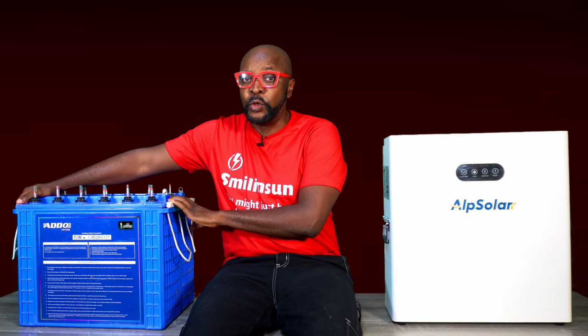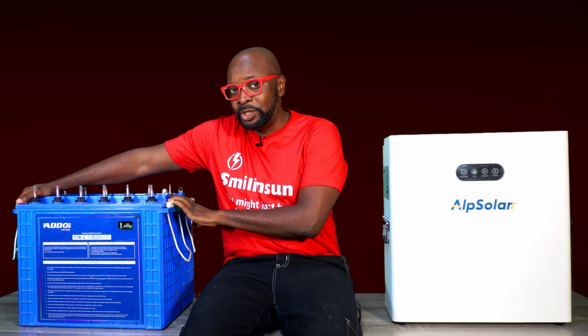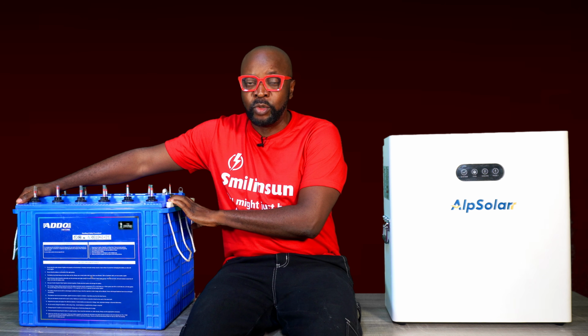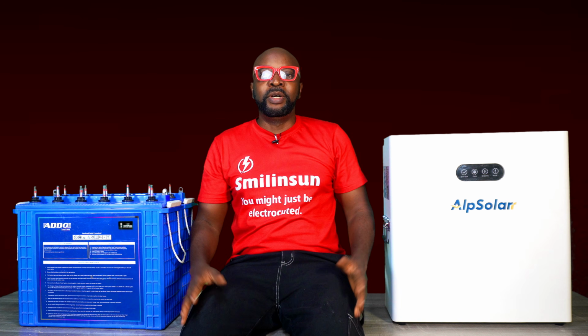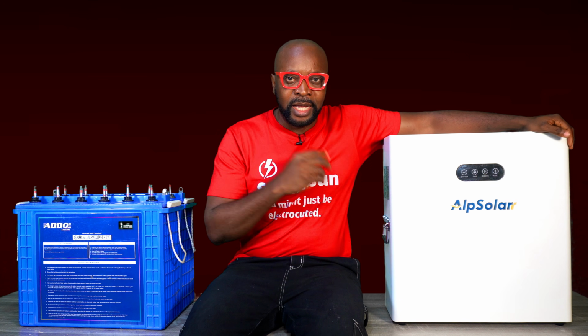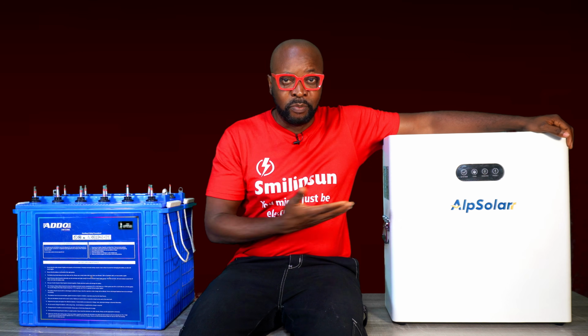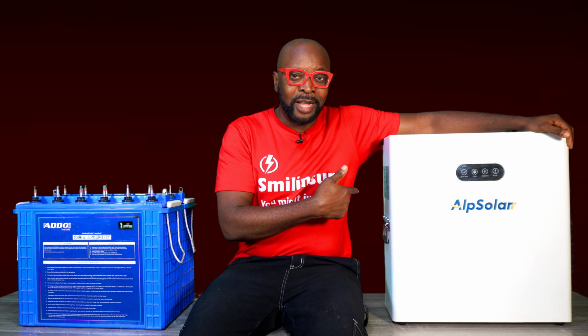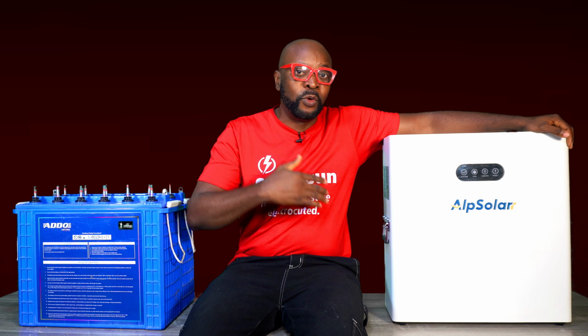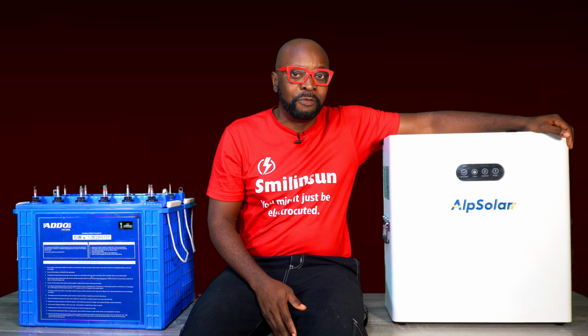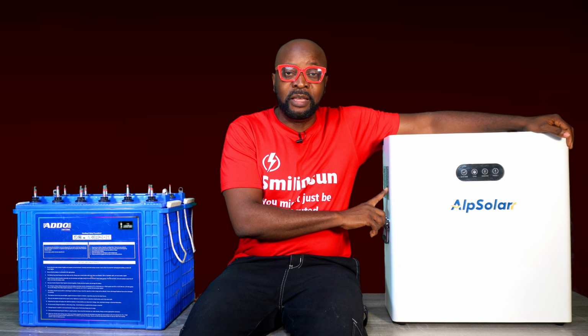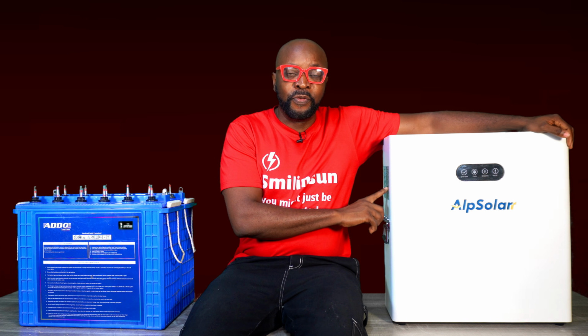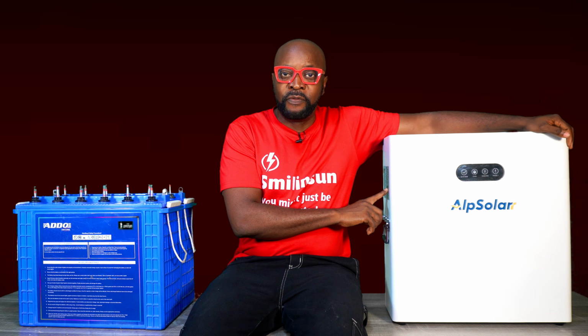It must go through the bulk charge, absorption charge, float charge, and then back to equalization charge. But the lithium battery goes through only 2 cycles of charge, which is the bulk charge, and then it gets to float charge. It doesn't have to go through the 2 remaining cycles of charge, which helps it to charge even faster.